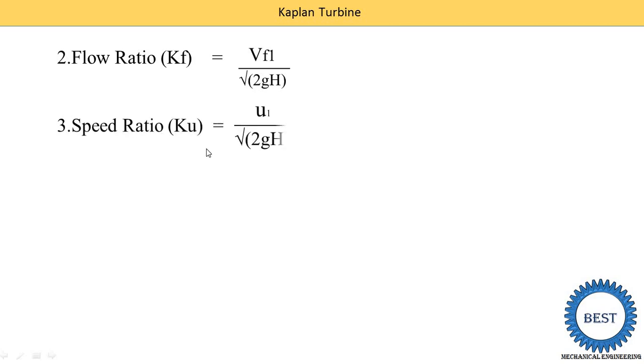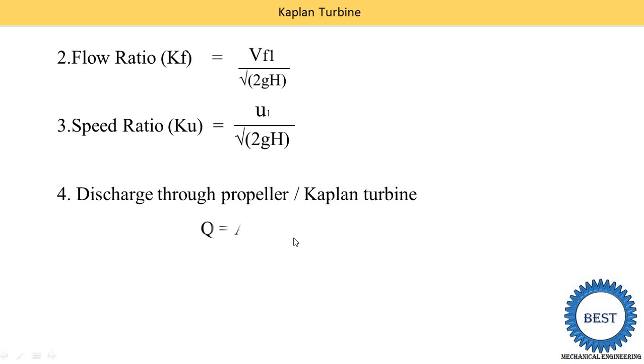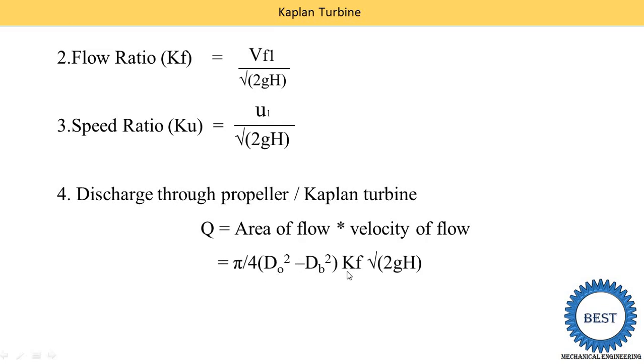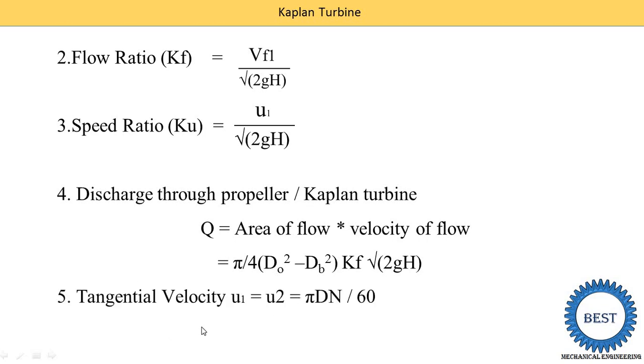Another equation is the flow ratio: Kf = Vf1 / √(2gH). The speed ratio is: Ku = u1 / √(2gH). Discharge for the Kaplan turbine is: Q = A × Vf, where A = (π/4)(Do² − Db²) and Vf1 = Kf × √(2gH). The tangential velocities are: u1 = u2 = π × D × N / 60. Using these equations, we are able to solve various problems and design the Kaplan turbine.